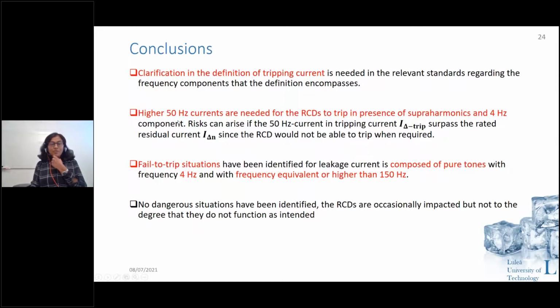Then second, in the presence of 4 hertz component and supraharmonic components, these two waveform distortions, a higher 50 hertz component was needed for the RCDs to trip. At least RCDs of type A already showed this kind of behavior. And fail-to-trip situations were seen when you have pure tones of higher than 150 hertz and 4 hertz in some cases. Okay, but overall we did not see a very dangerous situation with this much percentage of supraharmonics. I mean, we have gone up till 200%, but if you have a really high percentage of supraharmonics and it requires a lot more 50 hertz component to trip, then it could become a dangerous situation. But till now we have not come across that kind of dangerous situation.